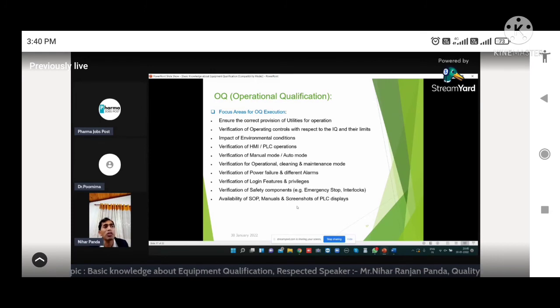Then verification of operational controls with respect to IQ. We have to check all the parameters also. Impact of environmental conditions, verification of PLC operations, verification of manual mode or auto mode during the OQ, you have to verify that also. Verification of operational, cleaning and maintenance mode. What is the operational mode and what is the cleaning mode? Like whether CIP, clean in place, is available, and other feasibility. How to operate during the cleaning part, which part can be dismantled, which part cannot be dismantled. Those things need to be verified during OQ.